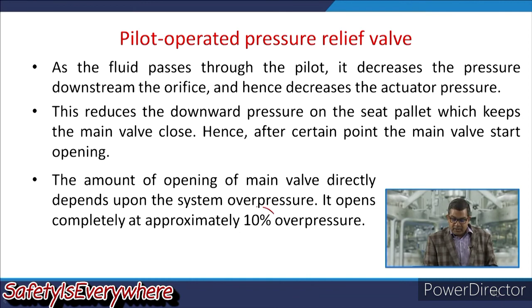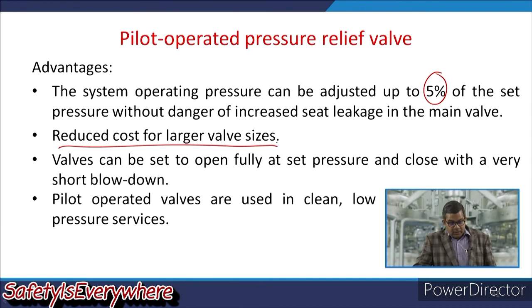There are several advantages associated with this pilot operated pressure relief valve. The system operating pressure can be adjusted up to 5% of the set pressure without danger of increased seat leakage to the main valve. They reduce the cost for larger valve sizes. Valves can be set to open fully at set pressure and close with a very short blowdown. The pilot operated valves are used in clean, low pressure services.